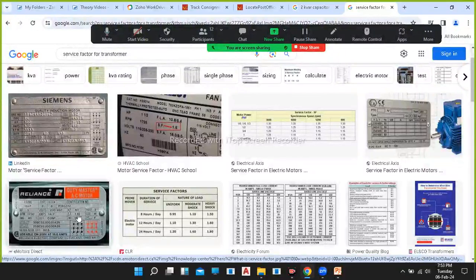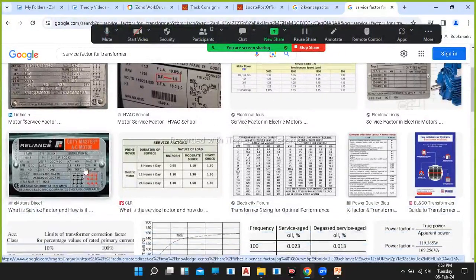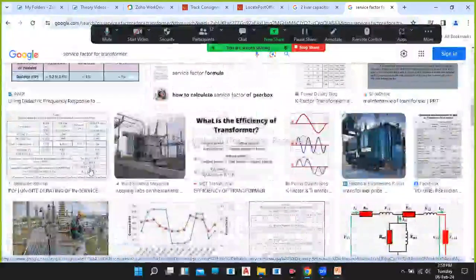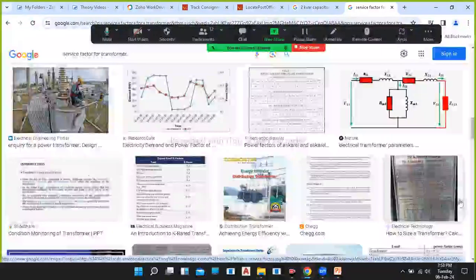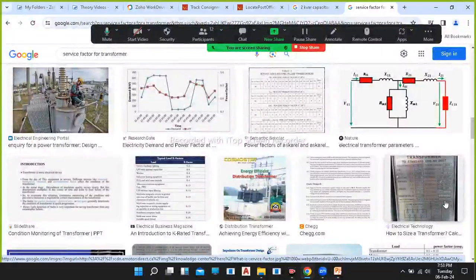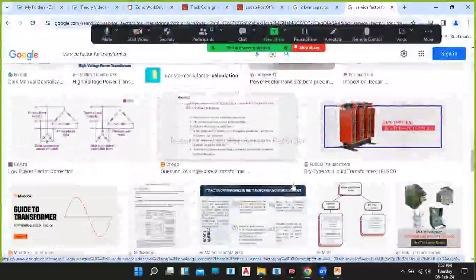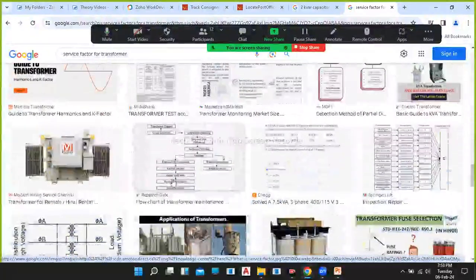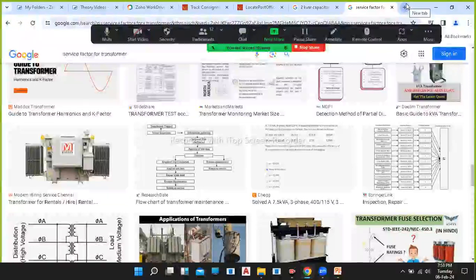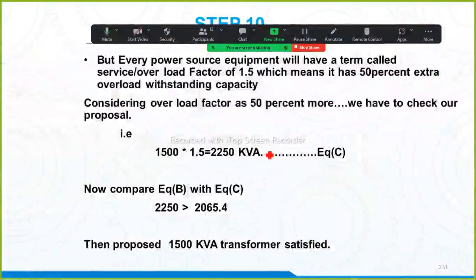दिख रहा है एवरीवन? Yes, sir. Okay, some equipment will have 1.2, some equipment will have 1.5, but 1.5 will be the maximum value. So if it is 1.2 then 1.2, if it is 1.5 then 1.5, based upon the demand factor, which lies between 1.1 to 1.5. Now I'm taking that suppose my equipment has 1.5 as a service factor or overload factor. इसका मतलब क्या है? What do you understand by that?